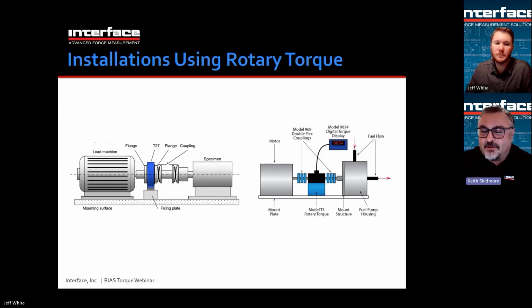Here we have some examples of rotary torque sensors. That specimen on the right could be a brake, could be another motor. On the left, we have a loading machine, which would be an electric motor in this case. You have a flange style torque sensor sitting in the middle, with flange adapters attached to each side of the torque sensor. We have couplings attached on the right side, and that's a double flex arrangement. And then, of course, your specimen. In the other picture, we have a motor and a fuel pump, and a pedestal mount torque sensor in the middle with double flex couplings on each side of the torque sensor.